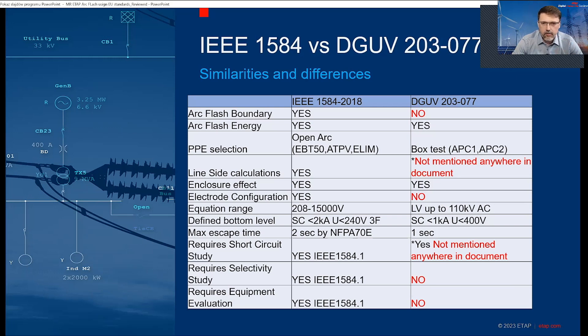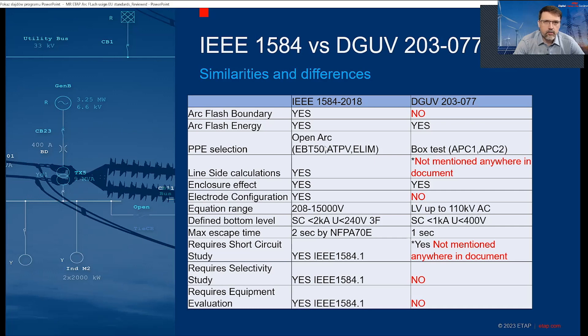Looking at the comparison: for IEEE 1584 we calculate arc flash boundary; for DGUV there is no arc flash boundary calculation — technically possible, but not really in the standard. Both calculate arc flash energy. PPE selection in IEEE uses open arc test — EBT50, ATPV, or ELIM for Europe. For DGUV it's the box method test: APC1 and APC2.